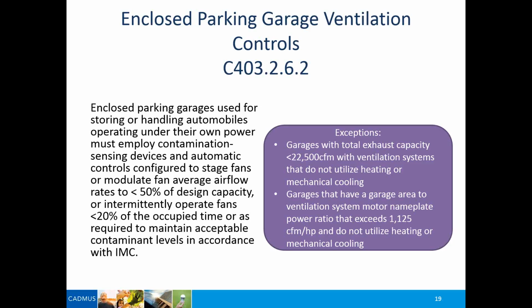So now, Howard, let's get into your requirement for Austin. For Austin, actually, we're bringing into Hawaii the same requirement that Austin has. This again is, I think, the key thing that Howard hit on, how you typically ventilate your parking garages through the trade winds. And this is specifically for enclosed parking garages, where you actually are bringing in mechanical ventilation air to make sure you're creating a healthy environment for the occupants in that space. And so the key thing is that you're reducing the amount of ventilation air in those parking garages when it's not needed.